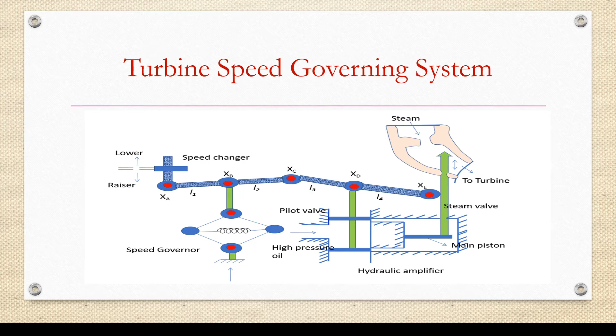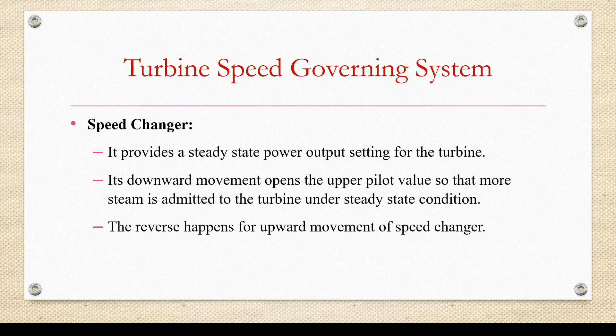Next is speed changer. Speed changer will provide a steady state power output setting for the turbine. Its downward movement will open the upper pilot valve so that more steam is admitted to the turbine under steady state condition, and reverse will happen for the upward movement of the speed changer.